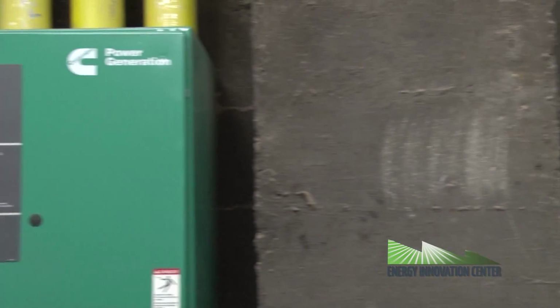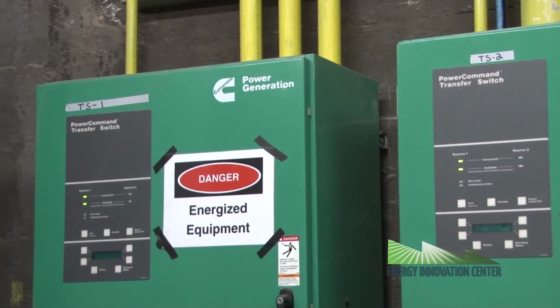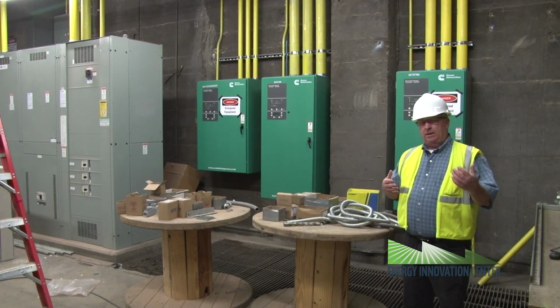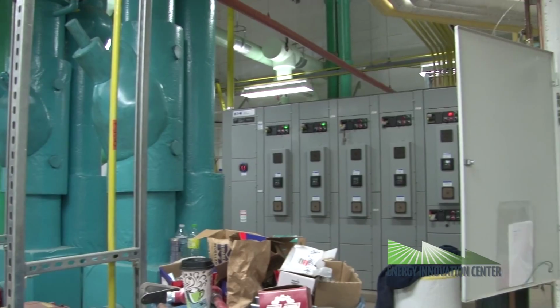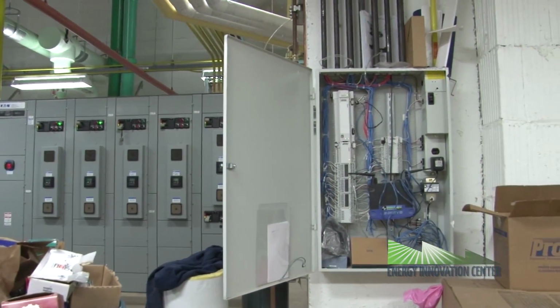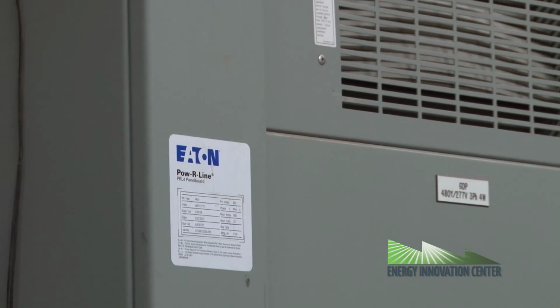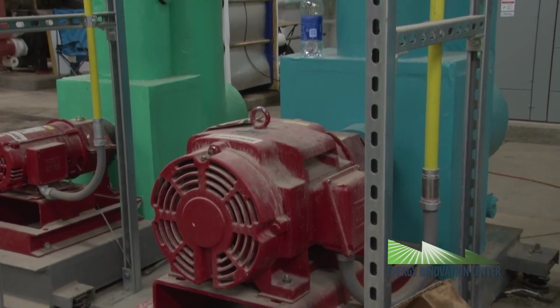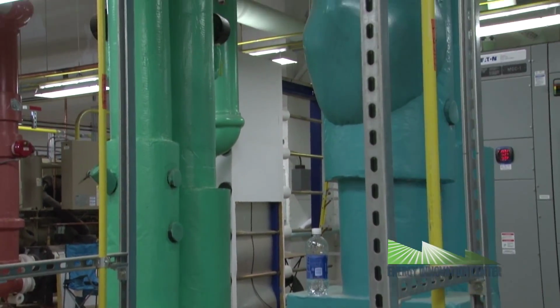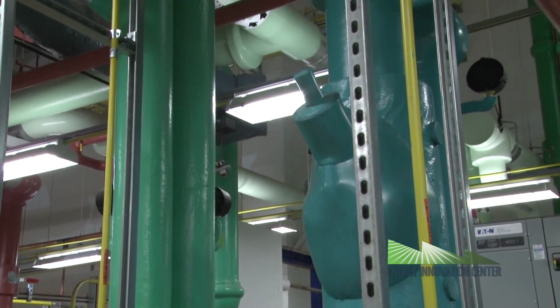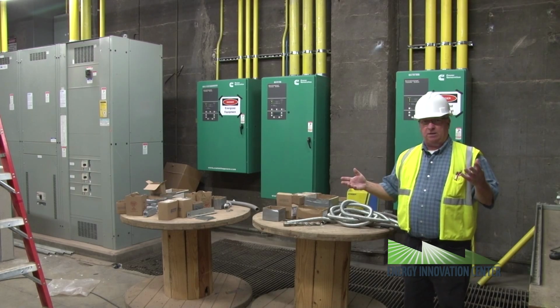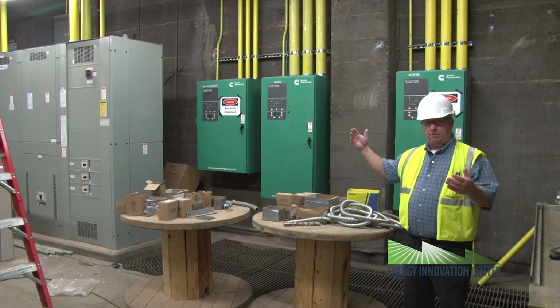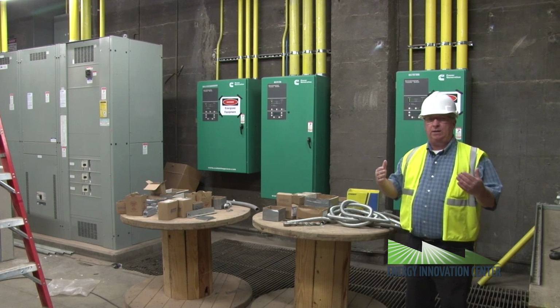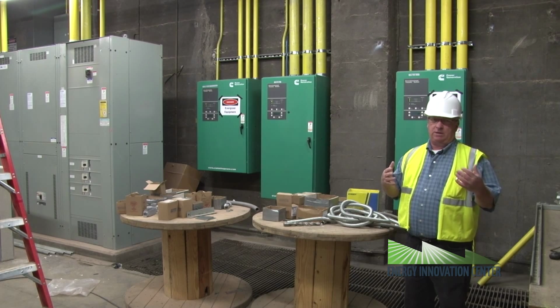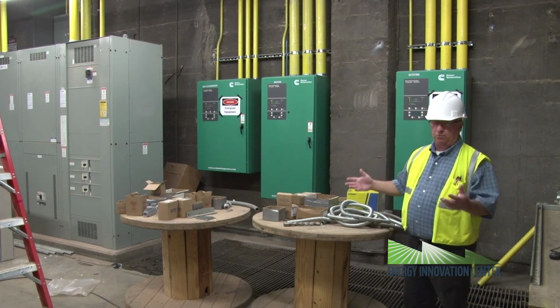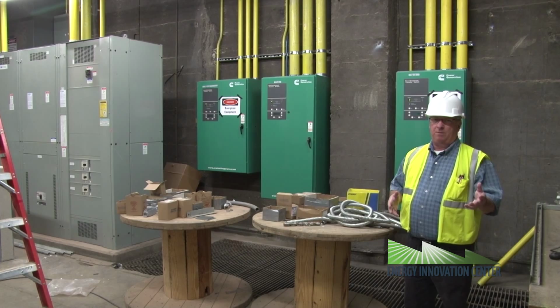The one thing that makes this building different from every other building we encounter is that when you lose power, the building automation system manages everything. We're able to manage the shutdown and restart of equipment based on power outages, and that saves energy. It minimizes issues—for example, if we lose one electrical leg, the building automation system can manage that. Typically the whole building would shut down, but we're able to shut down and isolate that equipment.